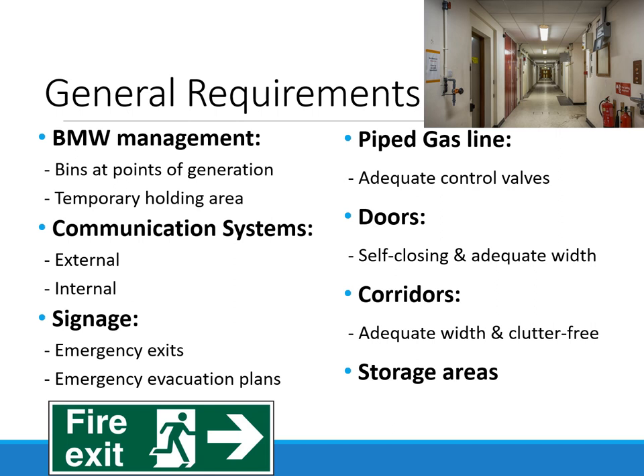There must be a robust communication system, usually with phones, for internal and external communication. Emergency exit signages and the emergency evacuation plan must be displayed for all laboratory personnel. The gas supply to the laboratory must be piped and should have control valves — this is preferred to gas cylinders as it reduces the risk of explosion. The laboratory must have self-closing doors of adequate width so that even large equipment may be brought in comfortably, and corridors must also have adequate width and should be clutter-free for easy evacuation in case of an emergency.